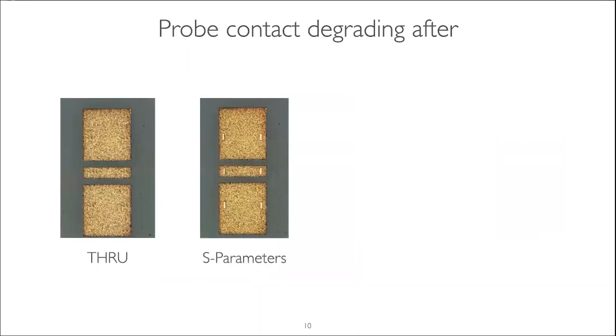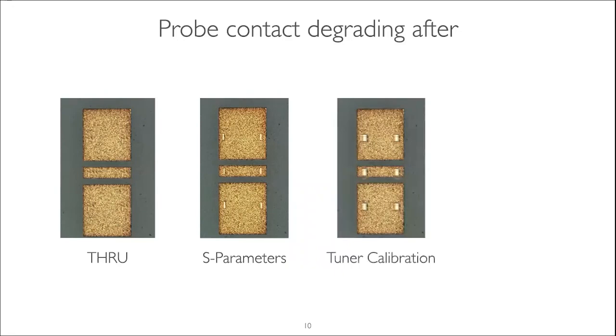Okay, so when you get a brand new thru, you're all excited, everything's clean, it's a perfect start. This is what the pads or the probe marks look like if, let's say, you want to do S parameters. In an S parameter measurement, you're basically lifting the probes up and down, you're landing, you don't need to dig in too hard, and it's a measurement that doesn't need to sit there for a very long time. Load pull is a very different thing. You need to sit down with the probe on the substrate for a very long time.